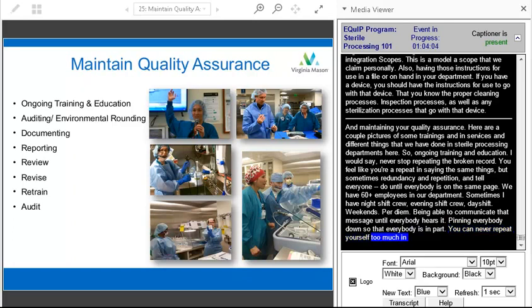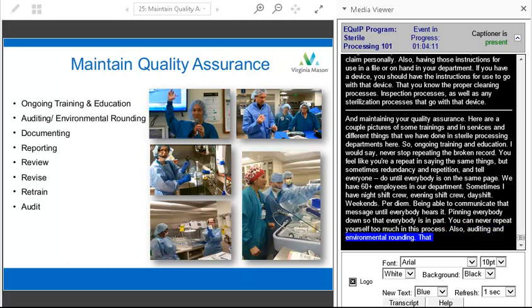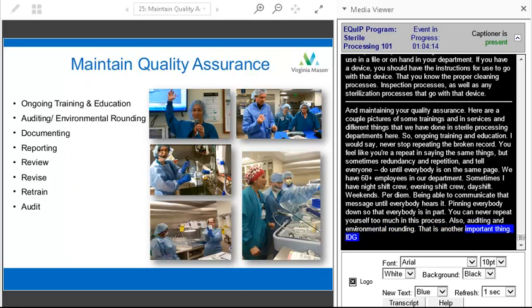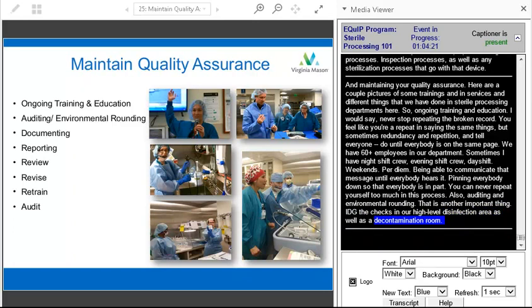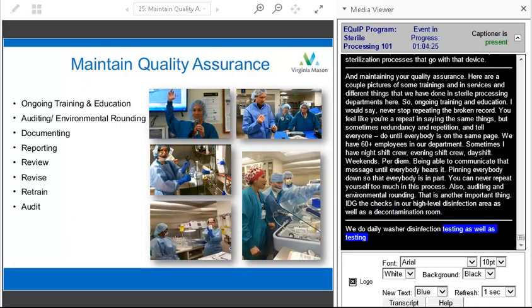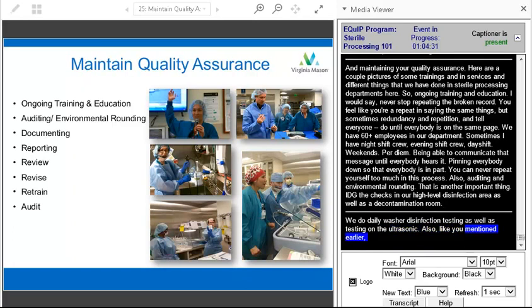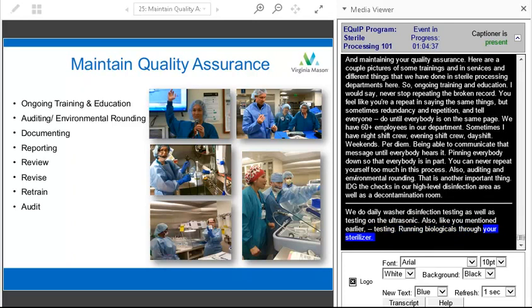Also, auditing and environmental rounding is another important thing. I do daily checks in our high-level disinfection area as well as the decontamination room. We do daily washer disinfector testing as well as testing on the ultrasonics daily. And also, like I mentioned earlier, Bowie-Dick testing on your pre-vacuum sterilization, running biologicals through your sterilizers, that type of thing. And then your environmental rounding.